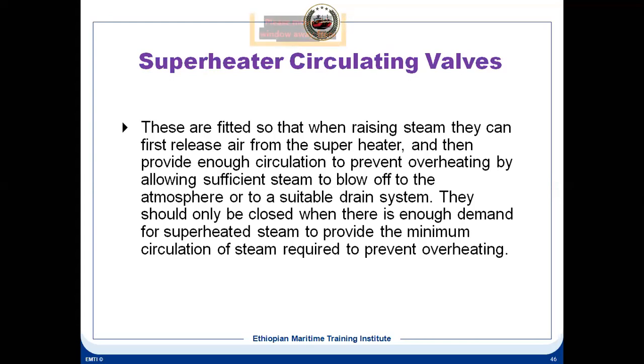They should only be closed when there is enough demand for superheated steam. That means you have a demand now for the steam to power a turbine, so then you don't need the superheater circulating valves. They should be closed only when there is enough demand for superheated steam to provide the minimum circulation of steam required to prevent overheating.